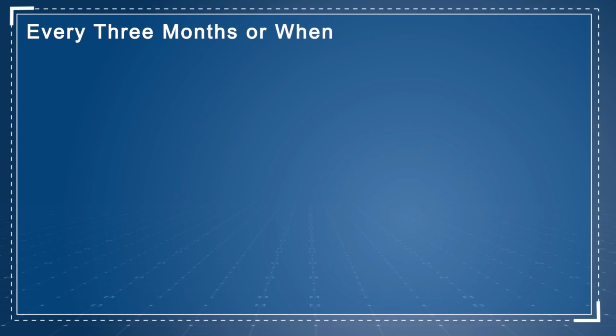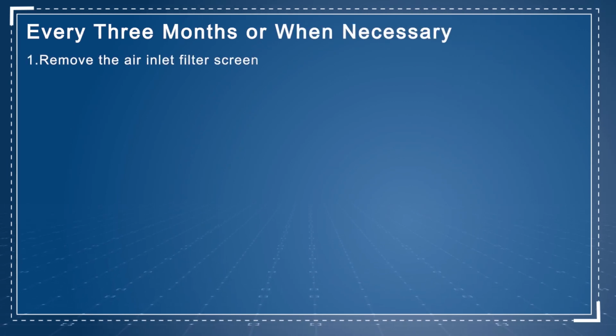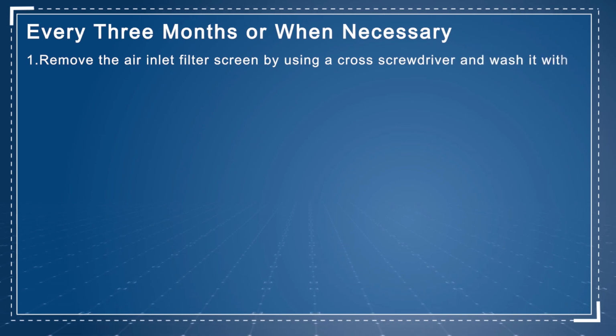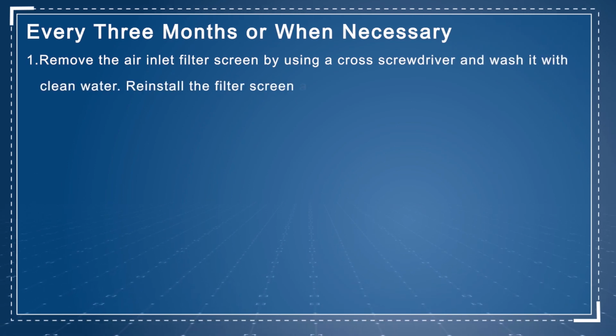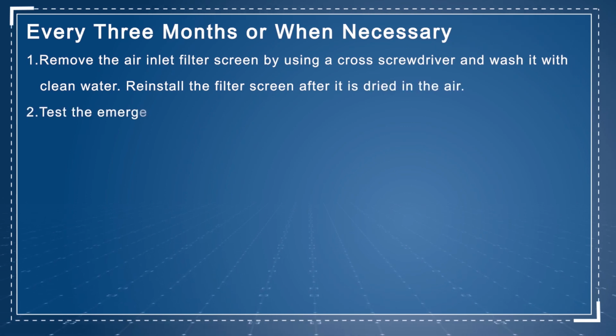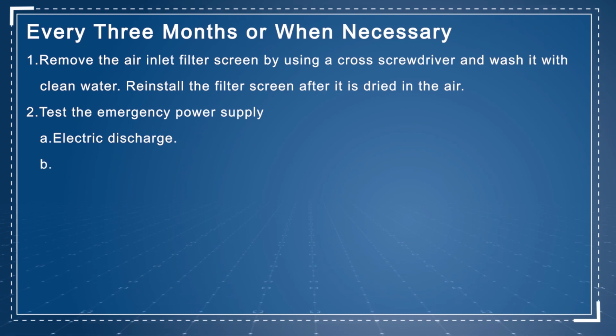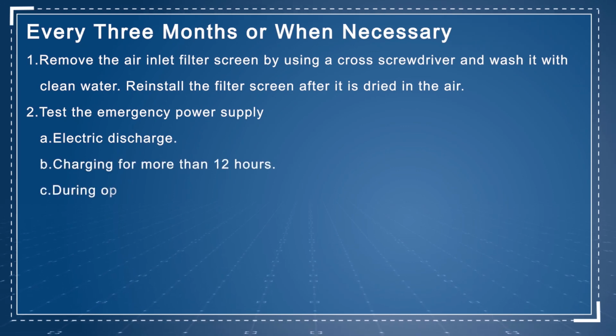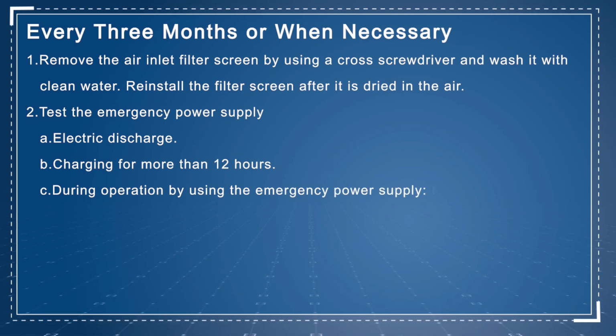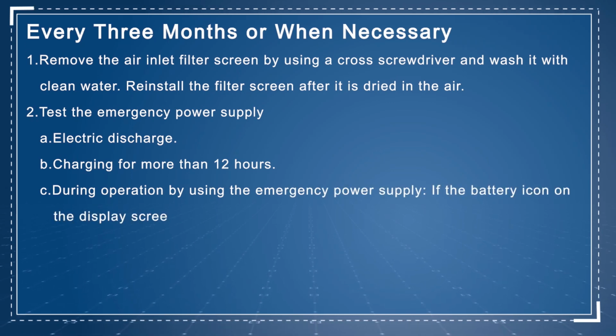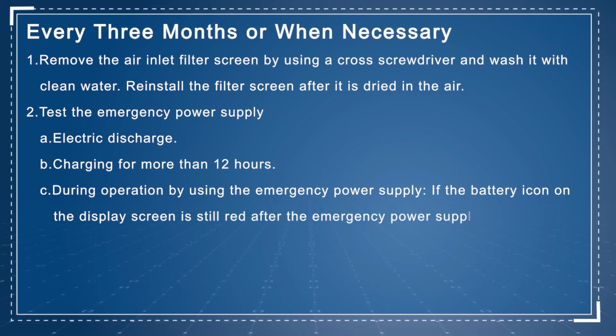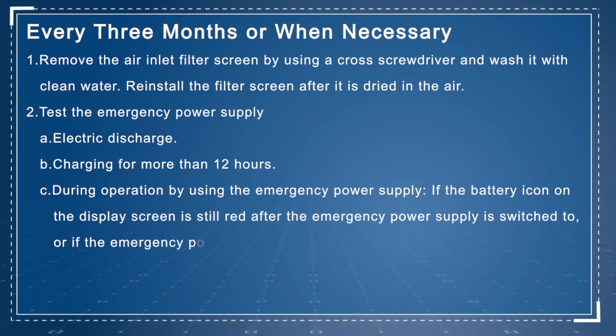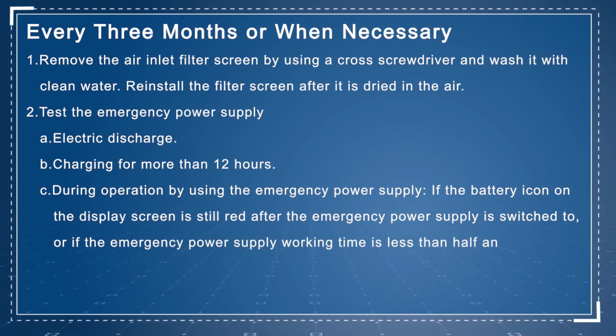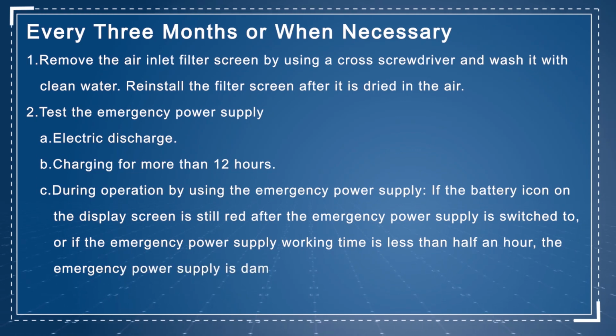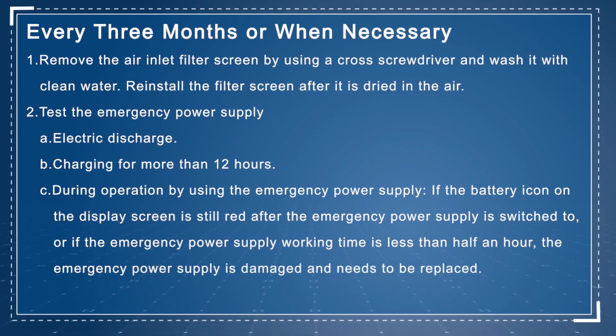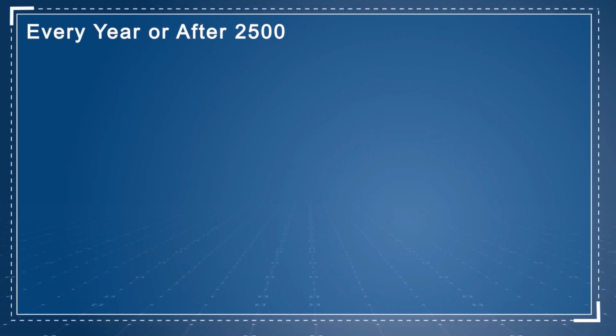Every 3 months or when necessary. 1. Remove the air inlet filter screen by using a cross screwdriver and wash it with clean water. Reinstall the filter screen after it is dry in the air. 2. Test the emergency power supply. A. Electric discharge. B. Charging for more than 12 hours. C. During operation by using the emergency power supply. If the battery icon on the display screen is still red after the emergency power supply is switched to, or if the emergency power supply working time is less than half an hour, the emergency power supply is damaged and needs to be replaced.